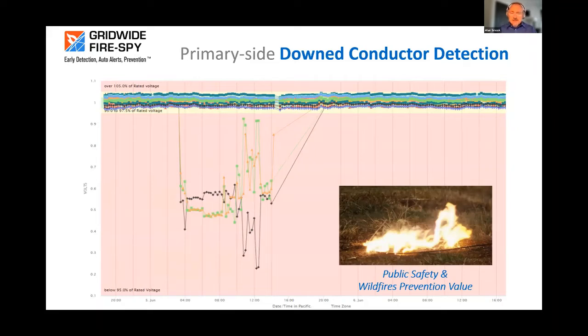Back in this 2020 era, we still were not even aware that our devices could pick up this kind of activity from the primary side impact. So as we autopsied the situation, we realized this data was captured not only by the polyphase device contiguous to this location, but downstream we had a single phase device similarly picking up the voltage drops that had occurred. So back in 2020, we did not have any alerting capability assigned to this type of extreme condition happening within a grid.